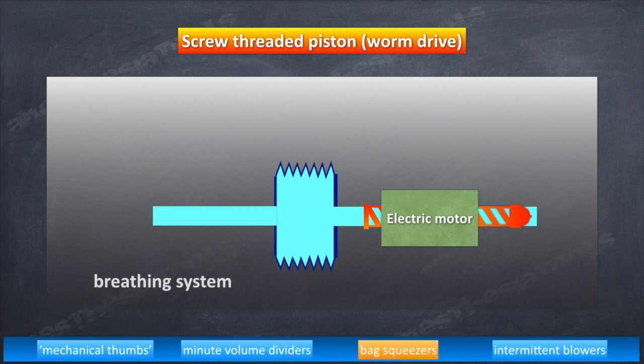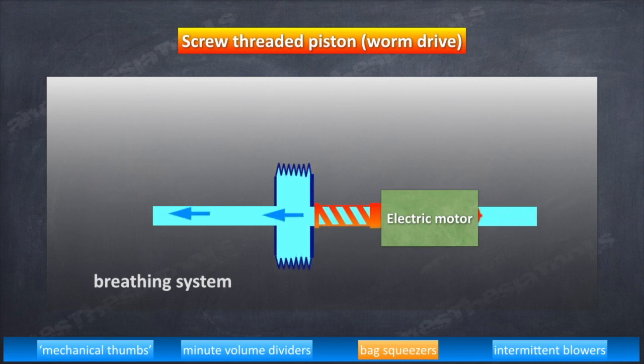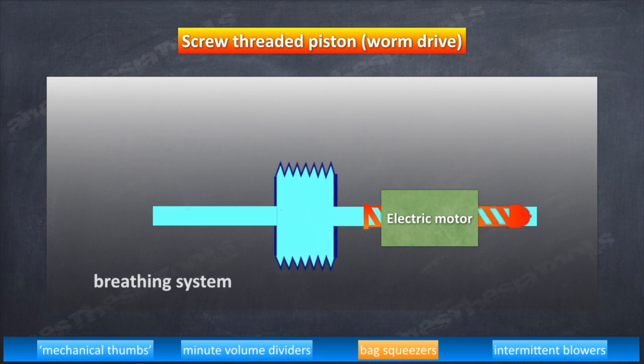Next, worm drive model. Here, bellows travel is produced by a linear travel of a worm gear driven by an electric motor. The speed of the motor can be altered both in inspiration and in exhalation to produce a variety of flows. This is a method used in Dräger E series of ventilators.